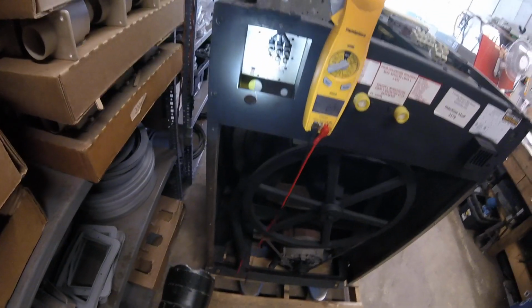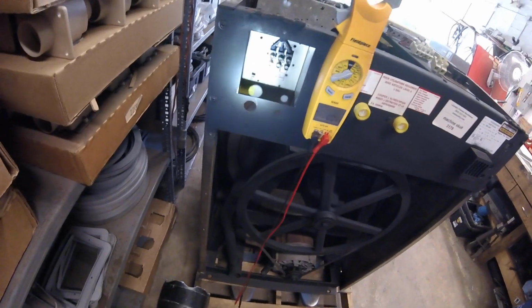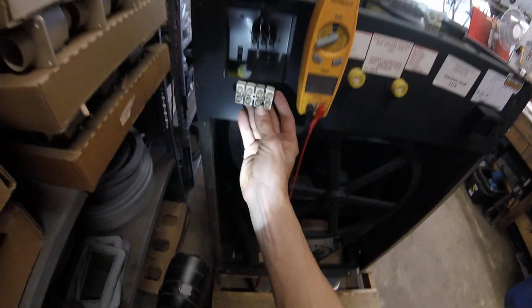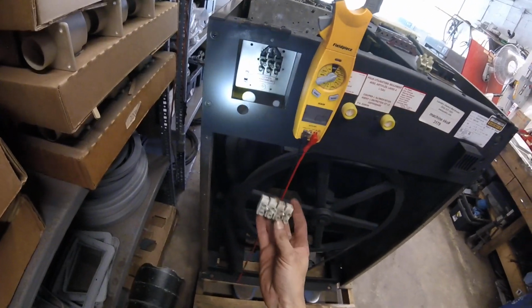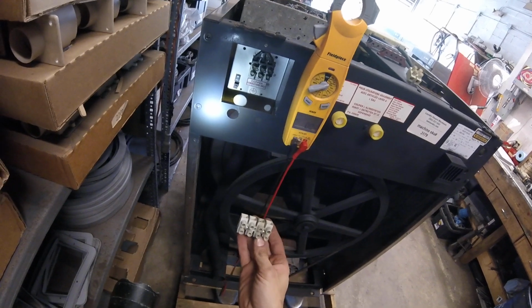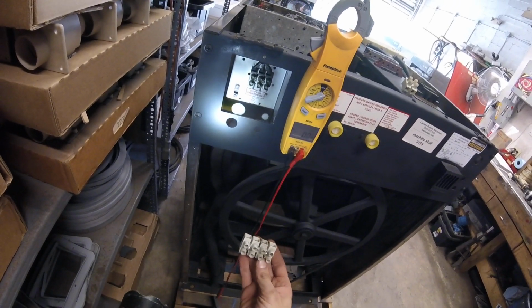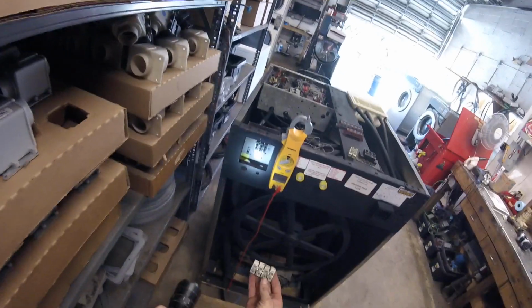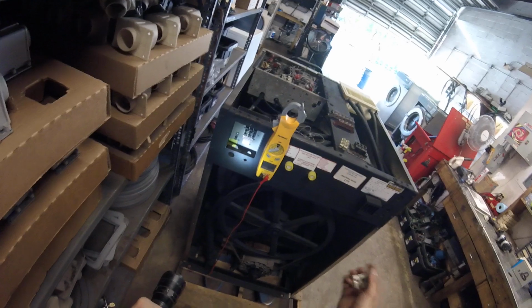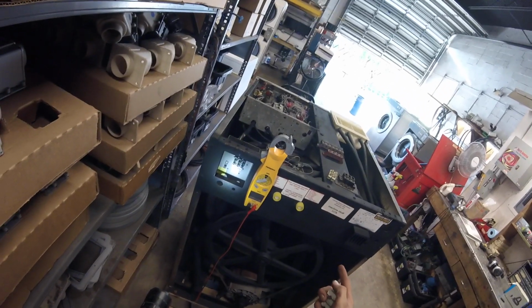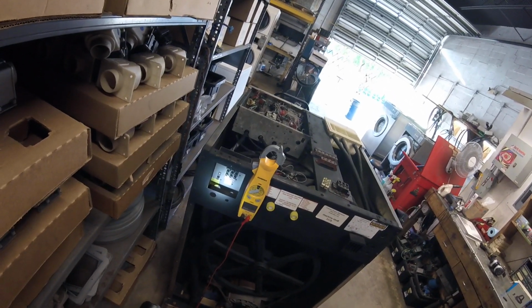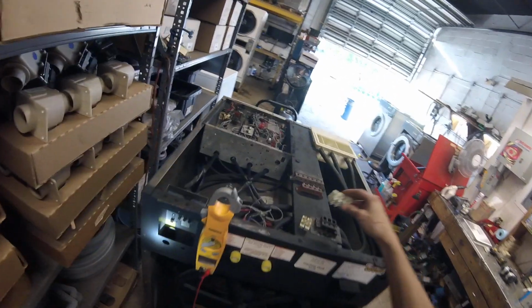Now, if you have a fourth wire and it's 220, but single phase, that means you have a neutral and a ground. You'll have a larger power terminal like this for the fourth wire. Now, you can, to make it work, jump neutral to ground, but do not leave the machine installed that way. There is a chance if something goes wrong with your wiring and the neutral wire gets broken, rather than working correctly and tripping your circuit breaker, it will energize the entire case of the machine and anyone touching it will be electrocuted. So neutral to ground is for testing only, it is not for permanent installation.